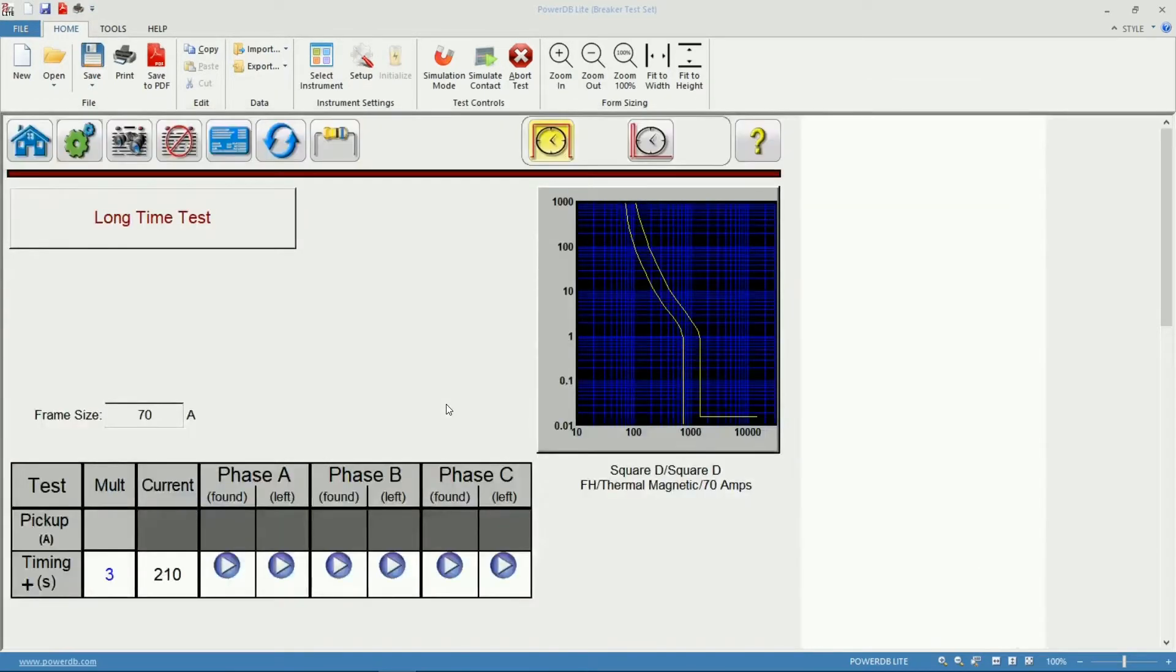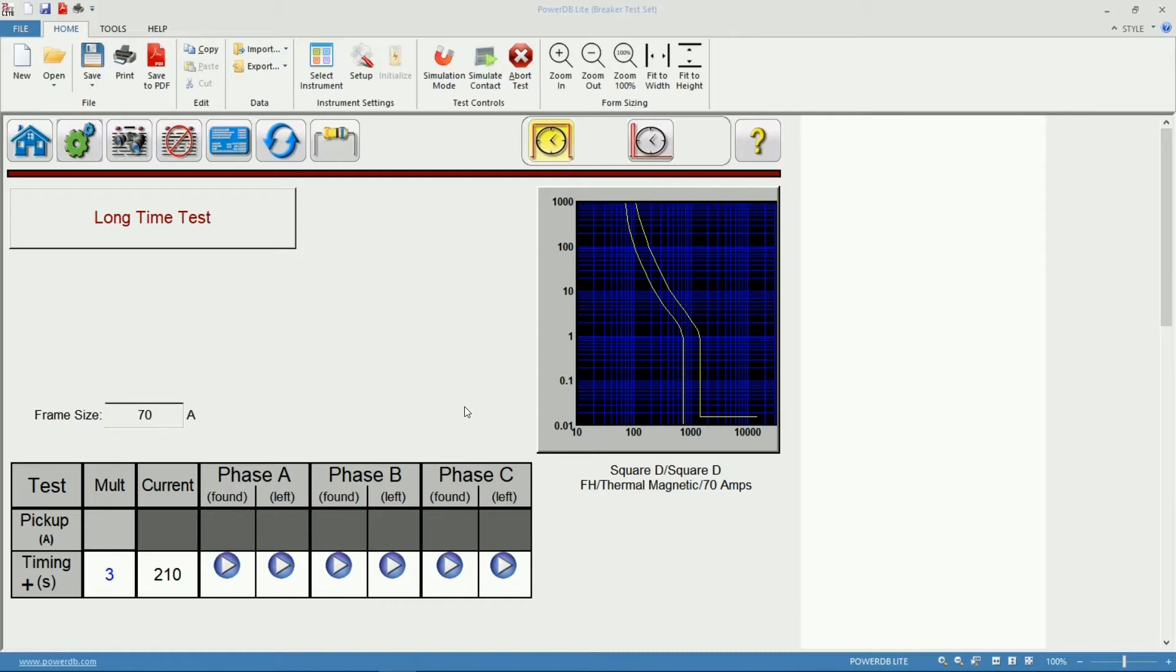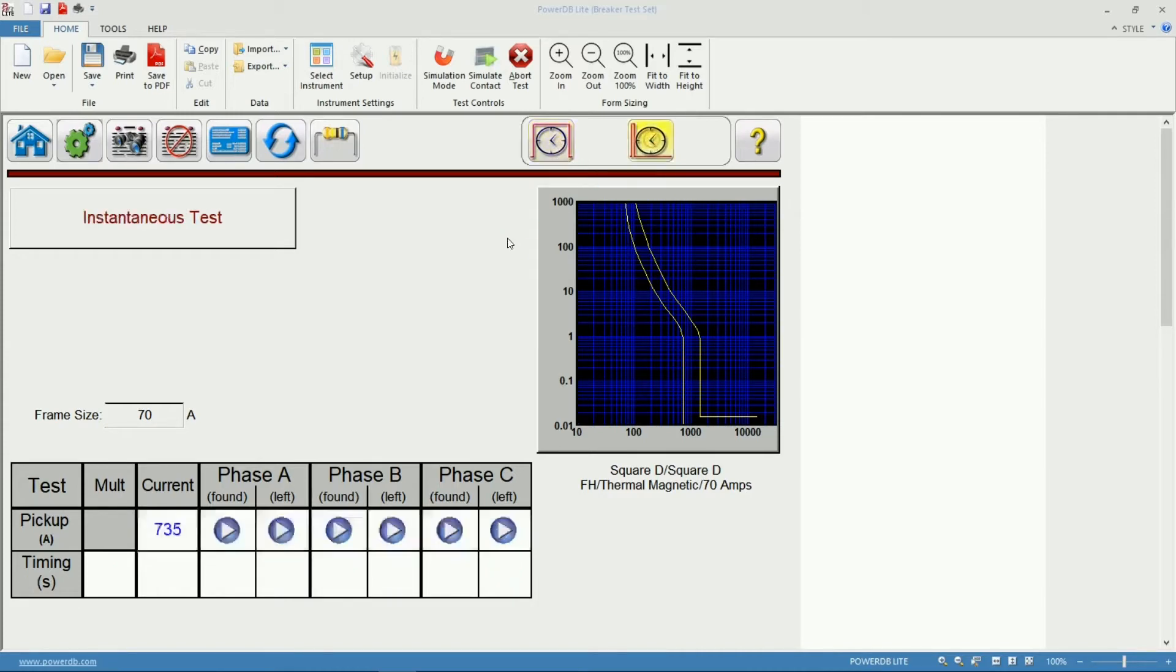The software will load the TCC for this breaker, the Time Current Curve for this specific model of circuit breaker. I can tell now that I will be able to test two elements on this breaker, my Long Time Test and my Instantaneous Pickup.